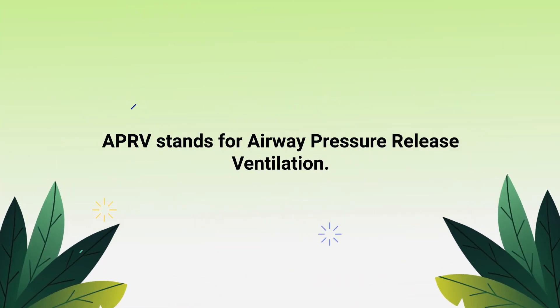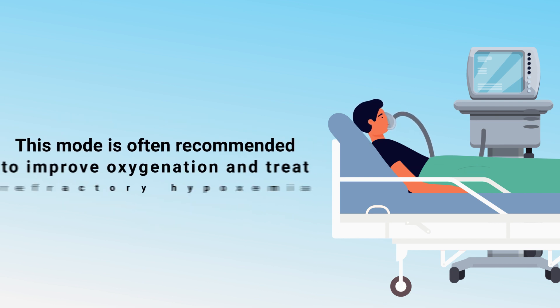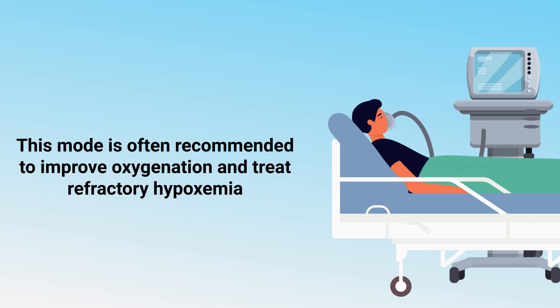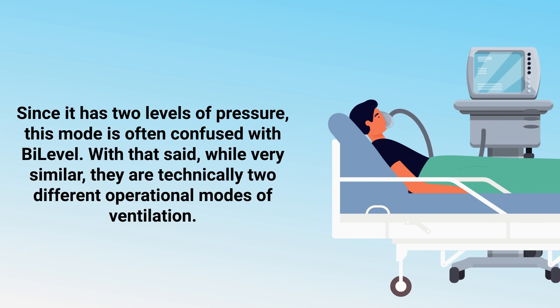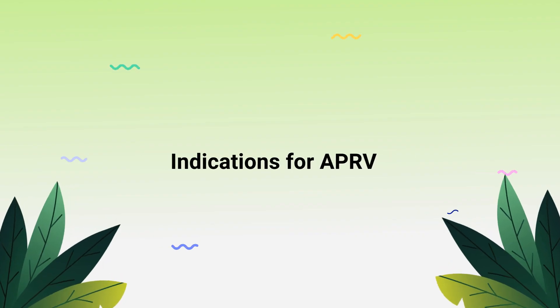APRV stands for Airway Pressure Release Ventilation. It's a mode of mechanical ventilation in which two levels of continuous positive airway pressure are applied with an intermittent release phase for spontaneous breaths. This mode is often recommended to improve oxygenation and treat refractory hypoxemia. Since it has two levels of pressure, this mode is often confused with bilevel — however, while very similar, they are technically two different operational modes of ventilation.